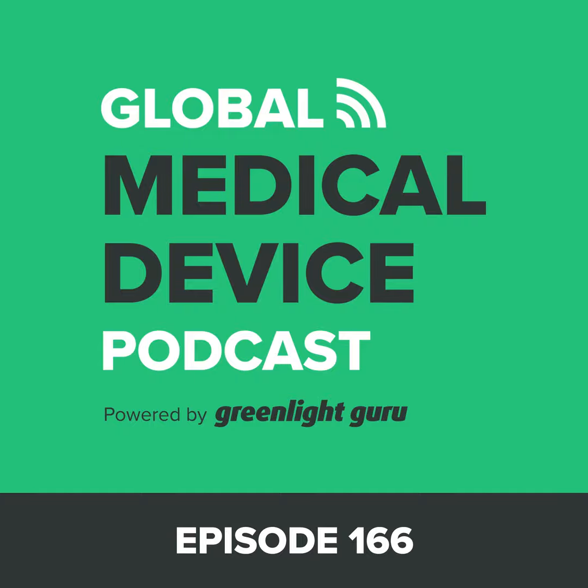There are a few topics that are ubiquitous and need to be addressed by every single medical device. And one of those topics is biocompatibility. I don't care if your product is non-patient contacting and is only software based, there's still something you need to address from a biocompatibility standpoint. I know it seems silly in those non-patient contacting type products, but you still need to deal with it and address it in some form or fashion.